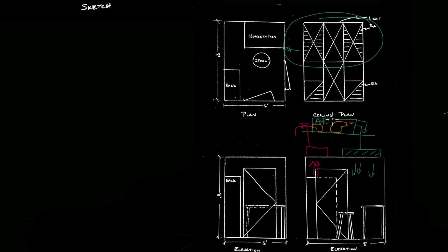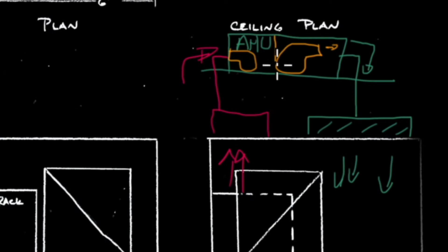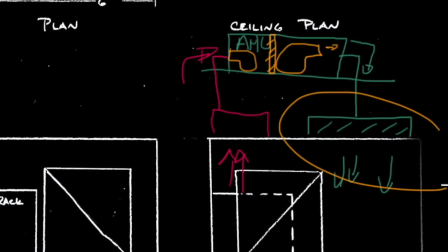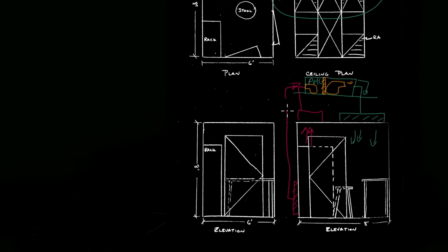The second feature that's often used in an air handling unit—let's zoom in a little on this air handling unit. Another feature we might add is a filter, which might go here. Generally for clean rooms, this fan filter unit is adequate at class 1000 or dirtier. But once we move to class 100, we need both filtering at the location and a pre-filter in the air handling unit. One further note: while my ceiling plan shows return air in the ceiling, my sketch also shows the possibility of return air grills down here, and then ductwork would have to route that return air back to the air handling unit.